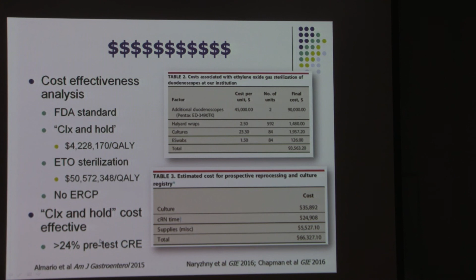Looking at cost-effectiveness analysis of several approaches, FDA standard, culture and hold versus gas sterilization versus no ERCP, culture and hold was only cost effective if the pretest probability of CRE was more than 24%. So clearly the big changes are coming, but we're not quite there yet. In the meantime, we should document reprocessing protocol. Training records should be semi-annual by AGA guidelines, possibly certification. It's very important that there is a way that an endoscope could be connected to the patient on whom it was used. Supplemental measures, as of right now, are not perfect, but it's all we have.